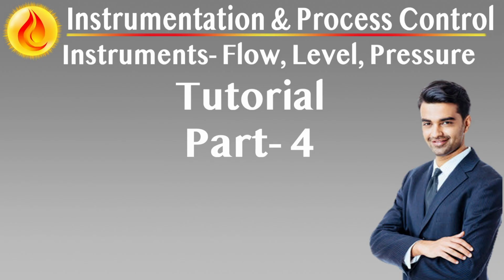Provide mechanical support for heavy meters and ensure adjacent piping exerts no torque or misalignment on the meter body. Calibration and proving considerations. For custody transfer or fiscal applications, turbine meters require regular proving using master meters or compact provers. Meters should be calibrated on the actual fluid or with a known standard to maintain accuracy. For critical services, double pulse pickups or redundant signal paths can enhance reliability and detect anomalies.